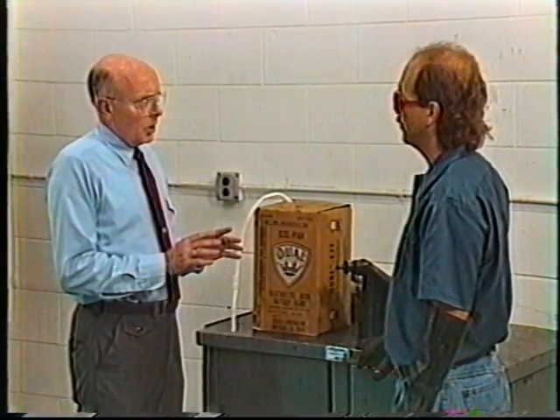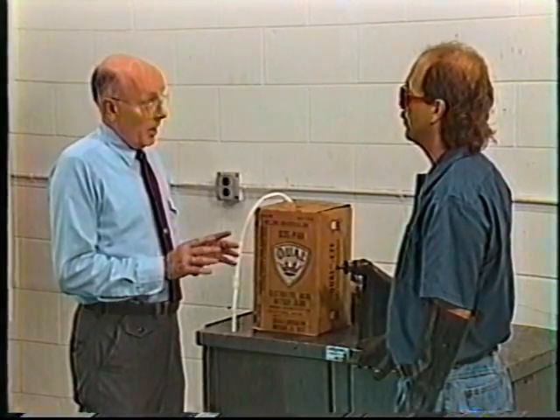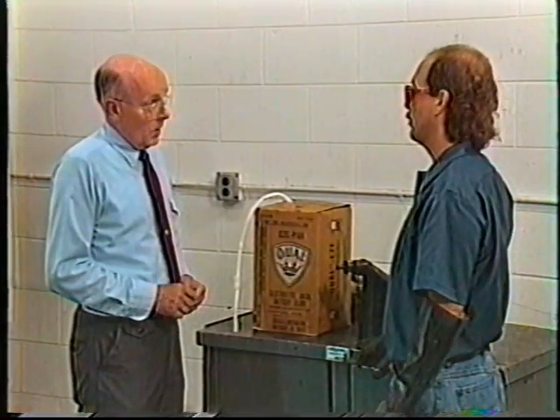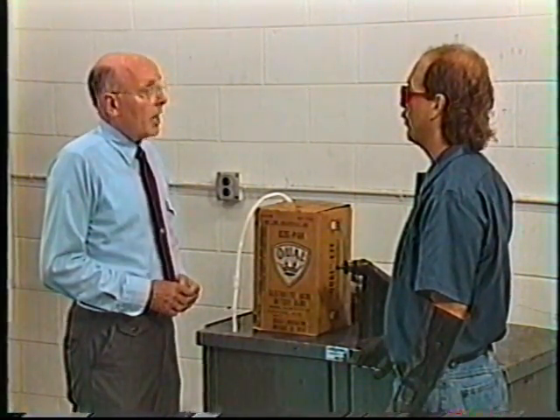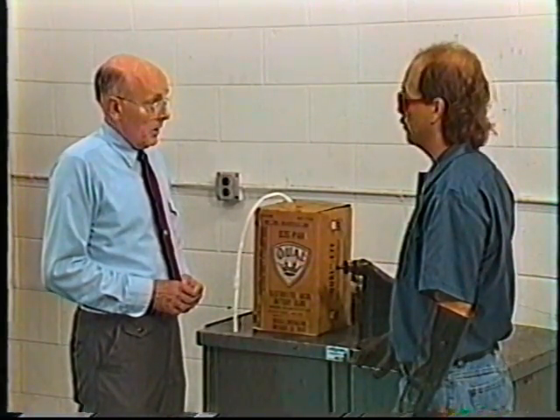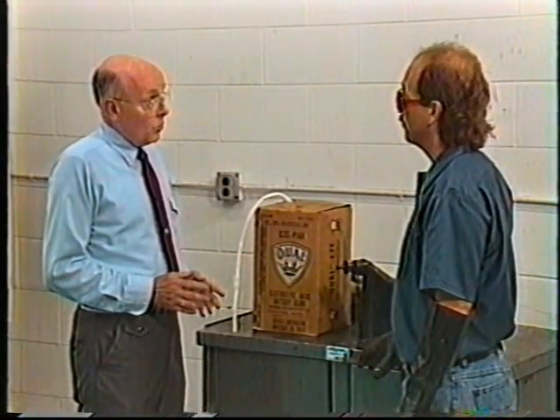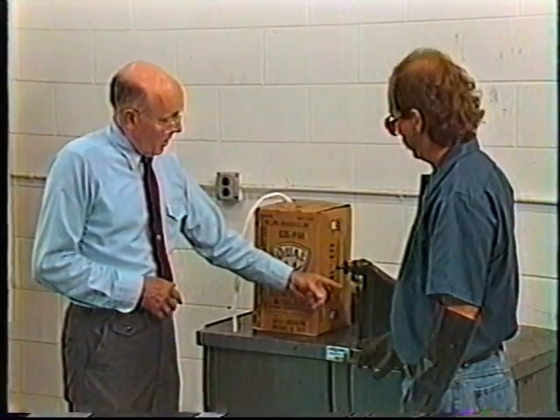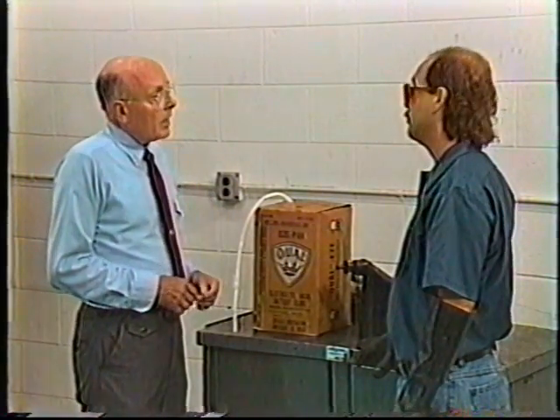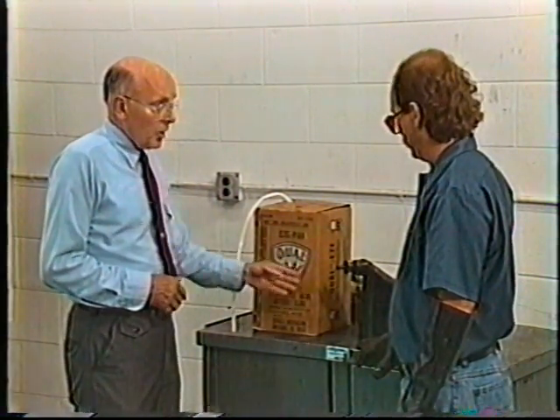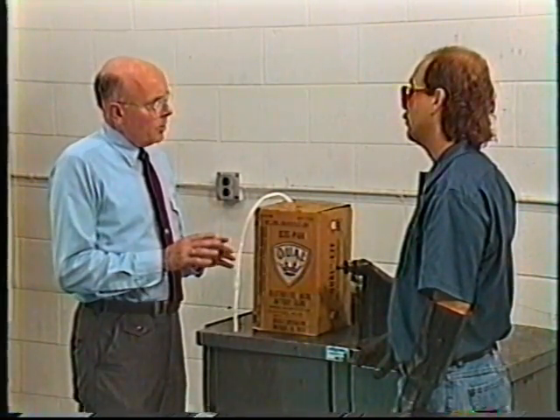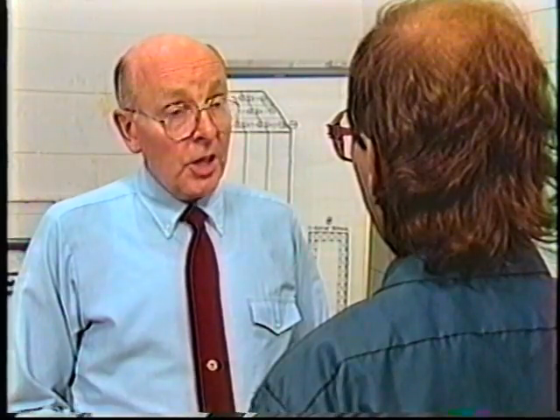Never use an electrolyte with a specific gravity reading higher than 1.400. The acid concentration is too high and it will shorten the life of the battery. If a cell's specific gravity reading is too high, we need to lower it by adding distilled water. In either case, whether you're adding electrolyte or distilled water, add only a few ounces at a time. In either case, always recharge the battery for an hour and a half before retesting.